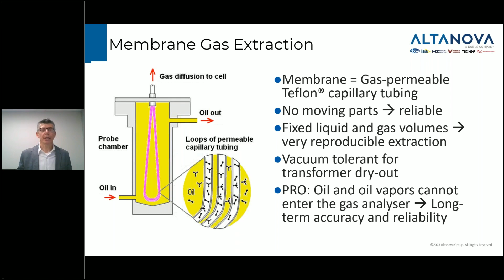And the big advantage really for me is that oil and oil vapors can never pass from the extraction vessel into the gas measurement system. And that's important for long-term accuracy and reliability of the gas measurement system, which is true whether it's a GC measurement system or an IR measurement system. Oil vapors are not conducive to long-term accuracy and reliability.